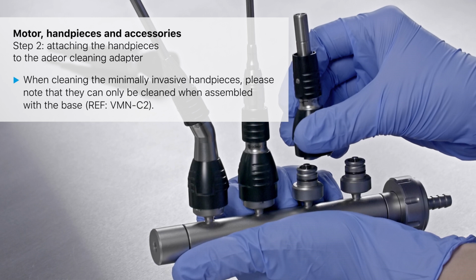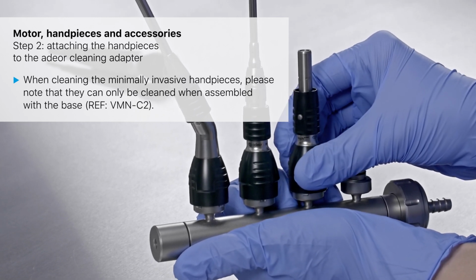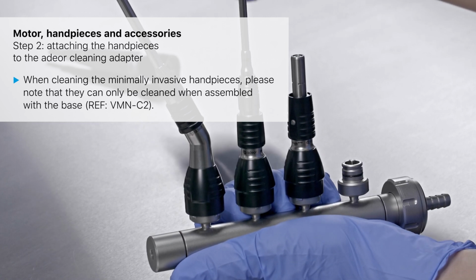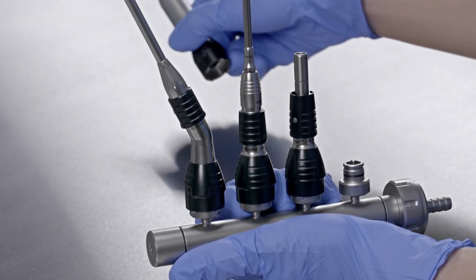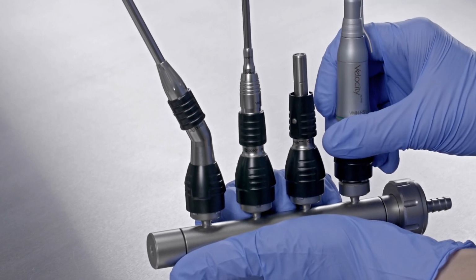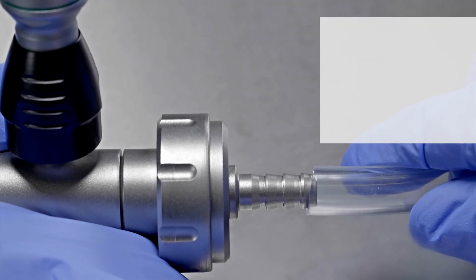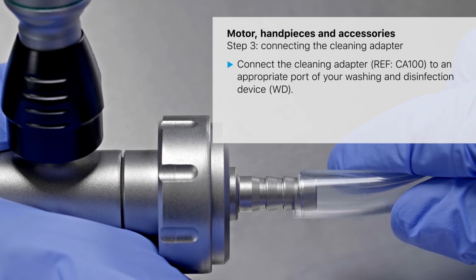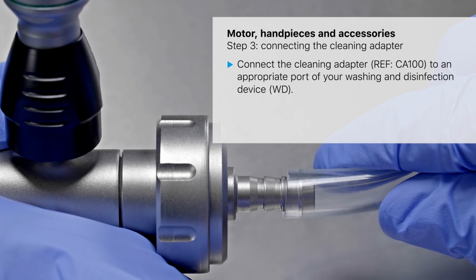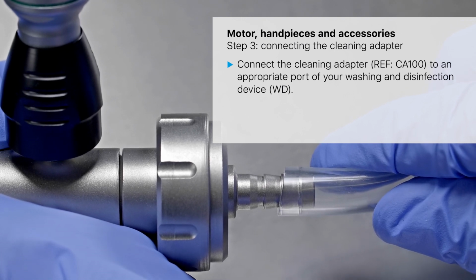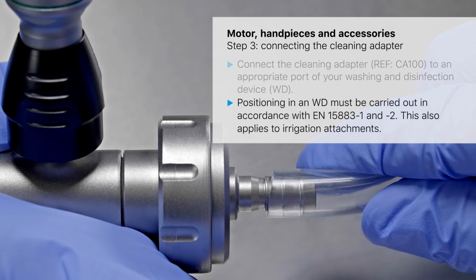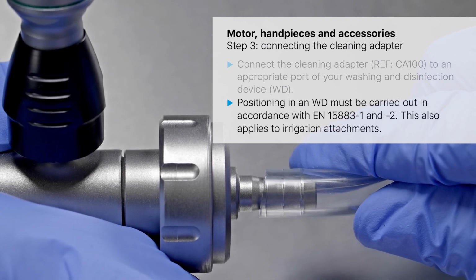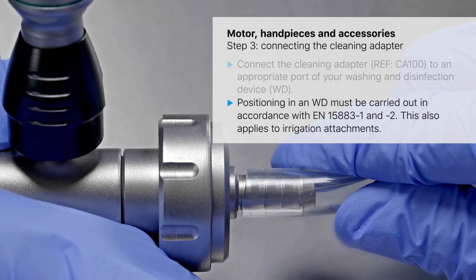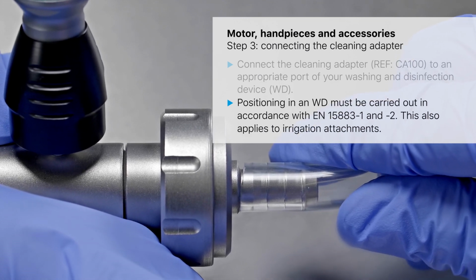When cleaning the minimally invasive handpieces, please note that they can only be cleaned when assembled with the base, reference VMN C2. Connect the cleaning adapter, reference CA100, to an appropriate port of your washing and disinfection device, WD. Positioning in a WD must be carried out in accordance with EN 15883-1 and -2. This also applies to irrigation attachments.